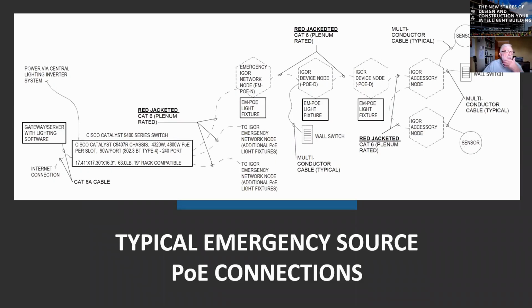We do the same thing for emergency, except for emergency we were using red jacketed cable. This says inverter, but it's really a UPS. You have to be careful with emergency lighting on POE that your power source doesn't drop out, because it doesn't take long at all for your switch to drop out and have to reboot. So that's just something to think about with your emergency lighting.